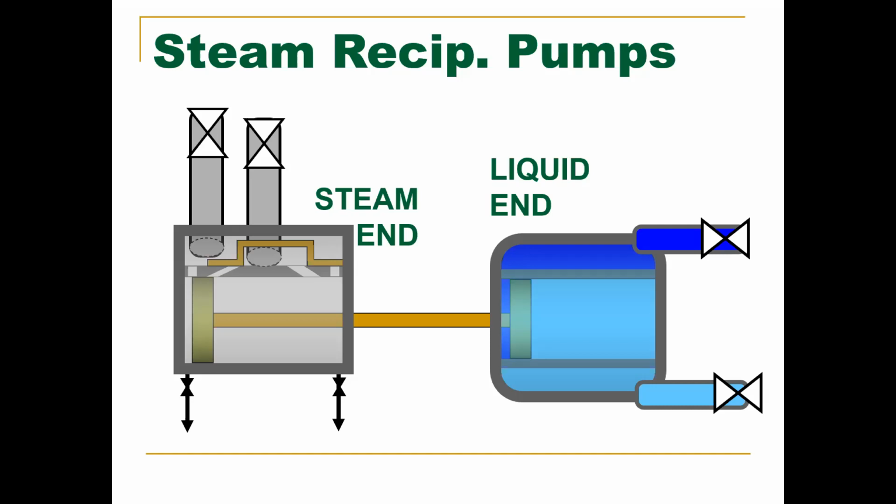Now, with a positive displacement pump, a lot simpler. All valves need to be open, including the discharge. Start the pump. Once the tank is filled, you secure the pump, then you shut all valves in the system. That's a quick reminder from what we did last Wednesday.